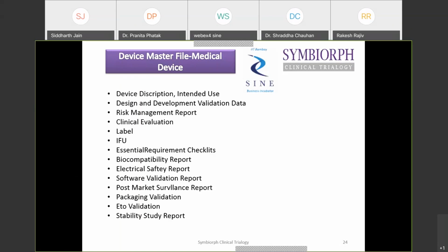Once you have submitted all your documents to the Sugam portal, then for class A and B, they have given the powers to the notified bodies to come and audit your facility and, depending upon the audit, recommend to the CDSCO the release of the manufacturing license. So the CDSCO inspectors are not going to come to do the audit. They have given the responsibility for class A and B to the notified bodies. The notified bodies currently registered in India are TÜV SÜD, TÜV Rheinland, DNV, Intertek. These are the 4-5 major companies which are currently doing the audit on behalf of CDSCO for the release of the manufacturing license as per the Indian Medical Device Rules.